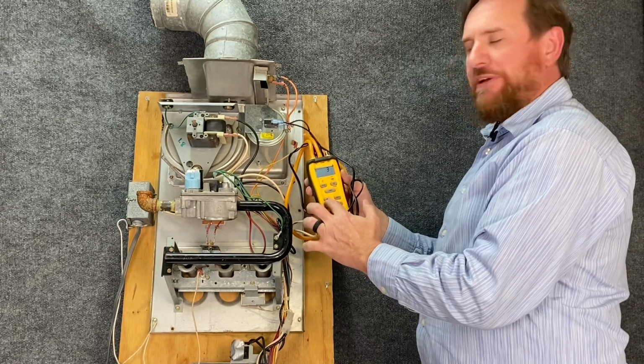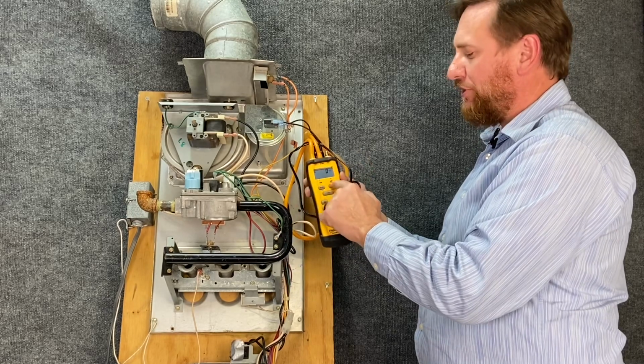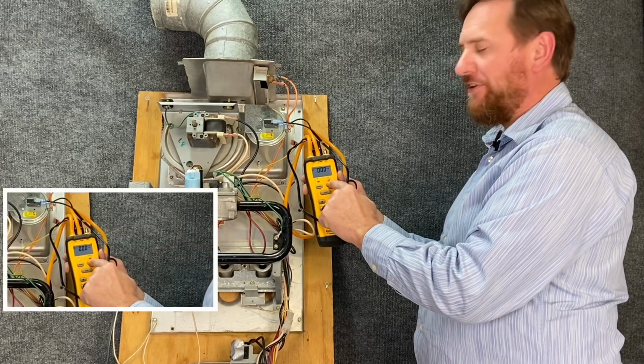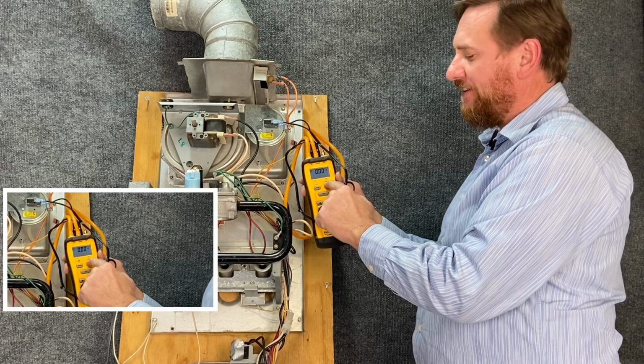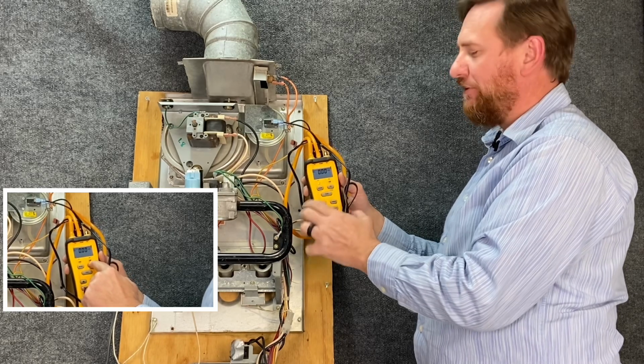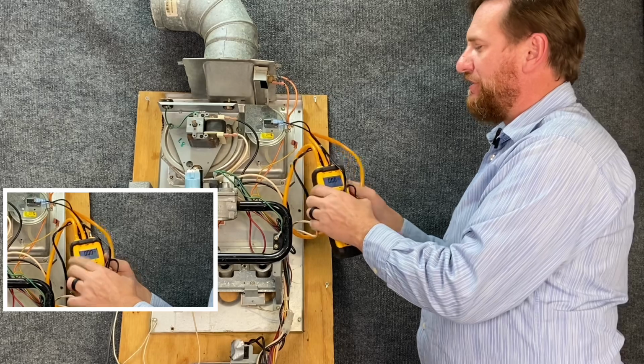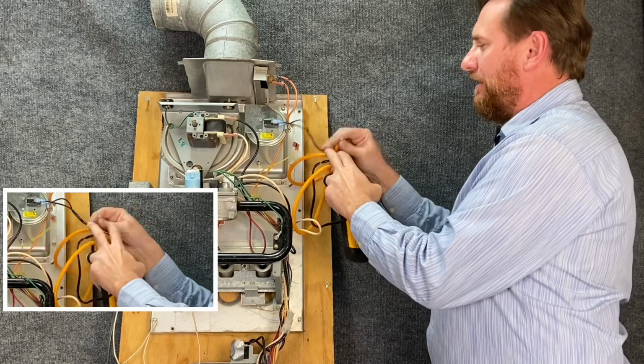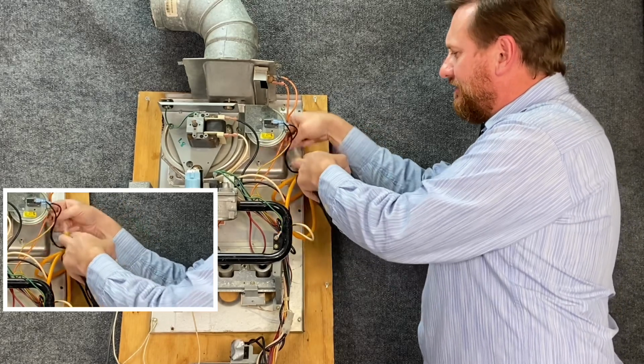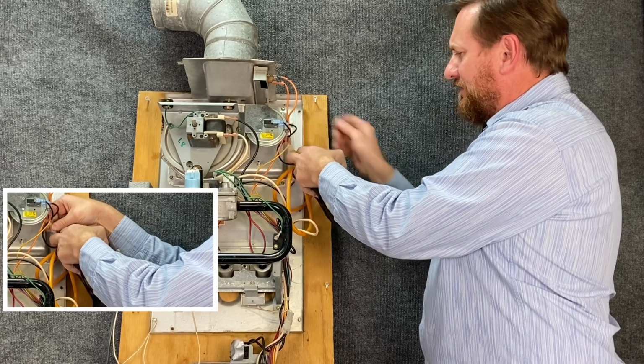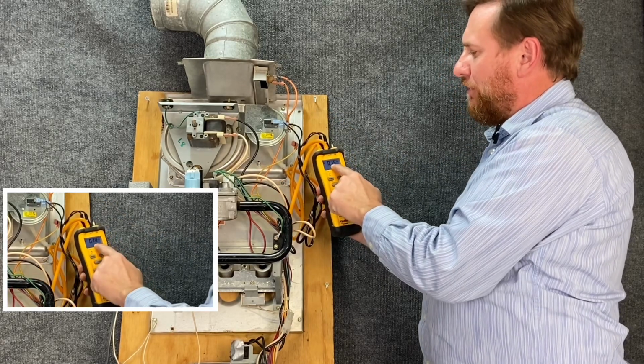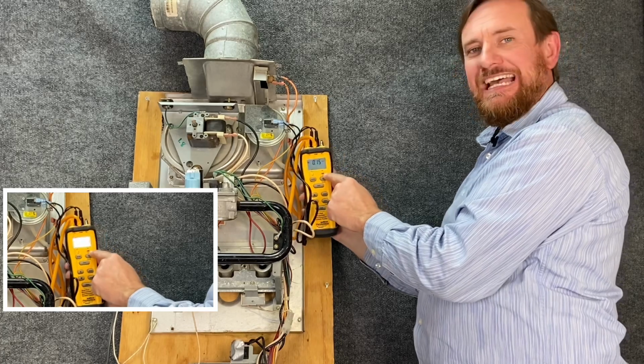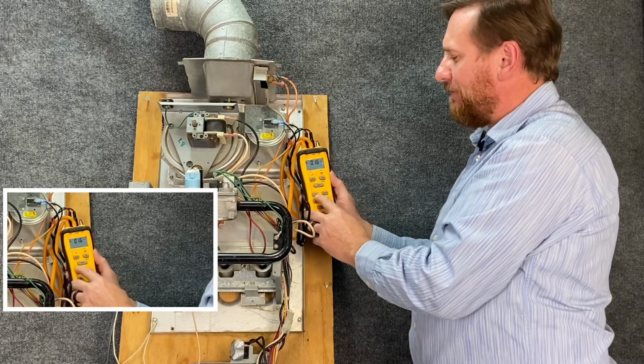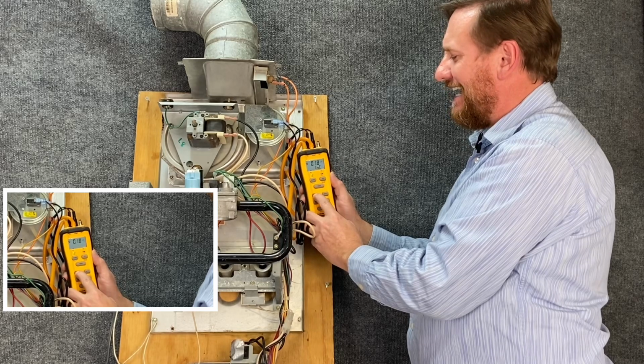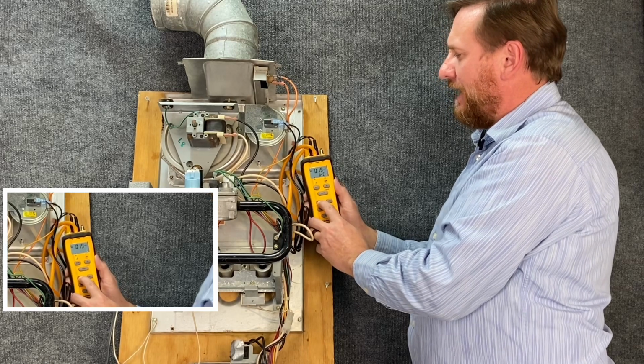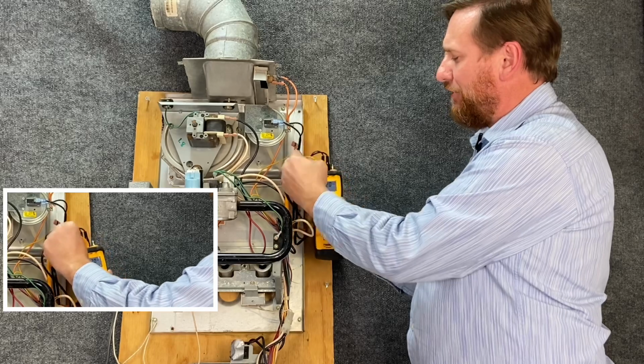I'm going to then increase the pressure until my switch closes. Here there's a little word that says close and a light above it. Once this light goes on, we know that that switch is without a doubt closed. Right now we have 0 inches of water column, and I'm going to plug my pressure switch into this T. So here I have 0.1 inches of water column. The light is off. So I'm going to increase my pressure. I'm going to press the up button, INC, increase. Now I'm at, we've got to make sure we're not kinked. My hose is kinked there.